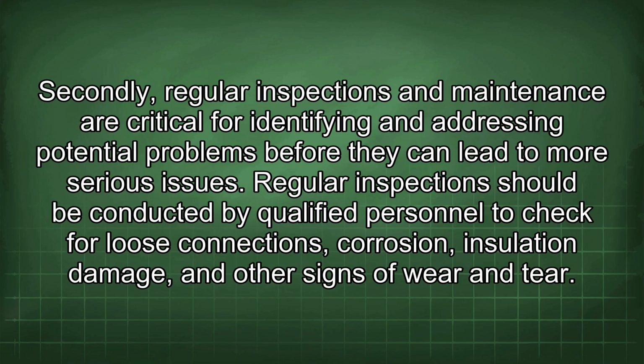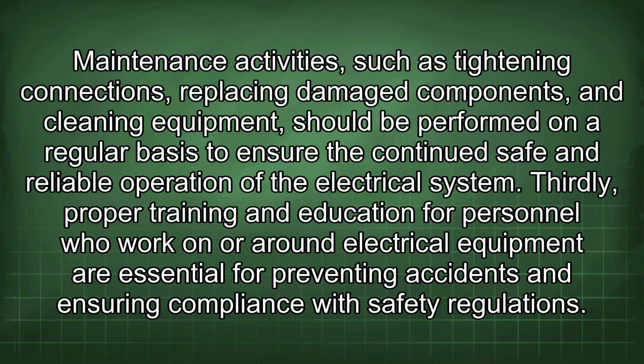Secondly, regular inspections and maintenance are critical for identifying and addressing potential problems before they can lead to more serious issues. Regular inspections should be conducted by qualified personnel to check for loose connections, corrosion, insulation damage, and other signs of wear and tear. Maintenance activities, such as tightening connections, replacing damaged components, and cleaning equipment, should be performed on a regular basis to ensure the continued safe and reliable operation of the electrical system.